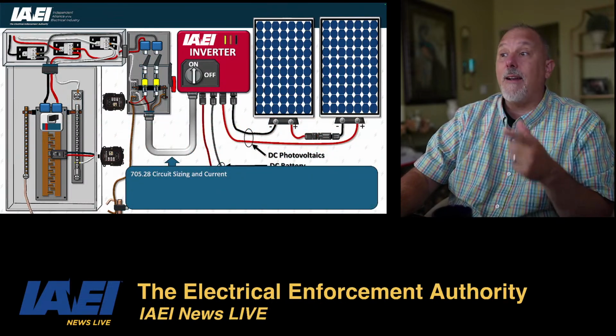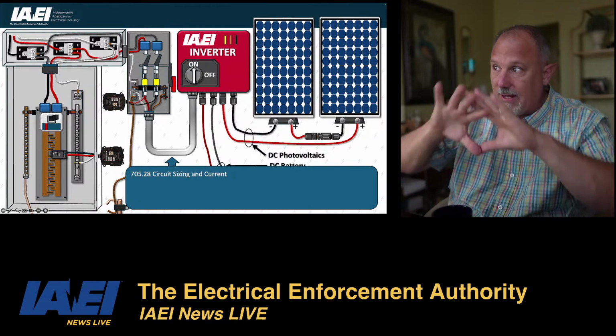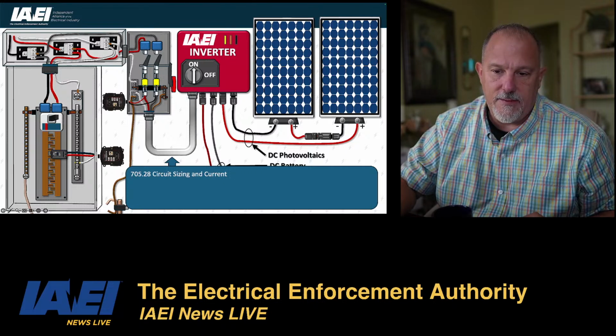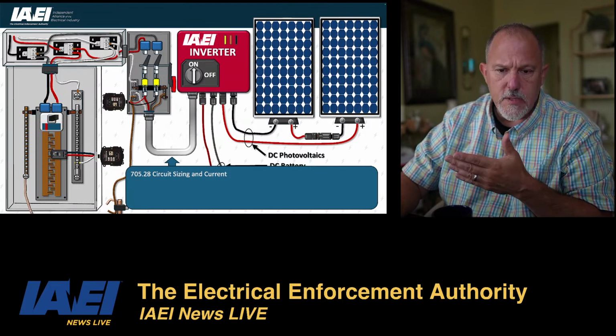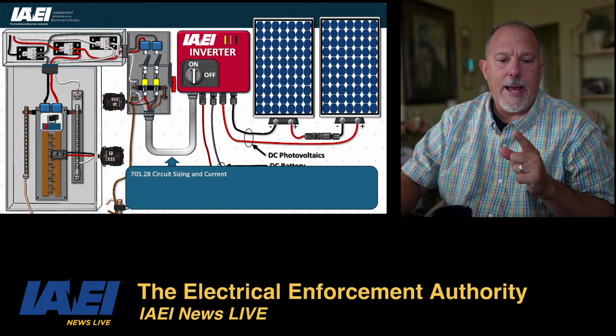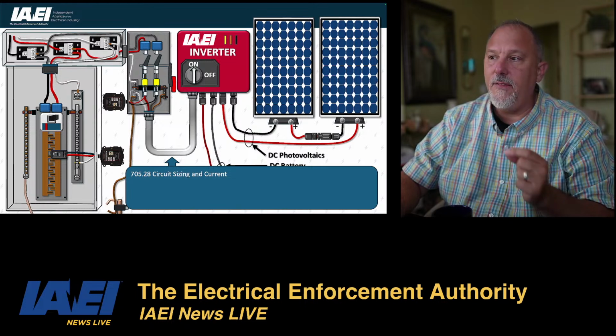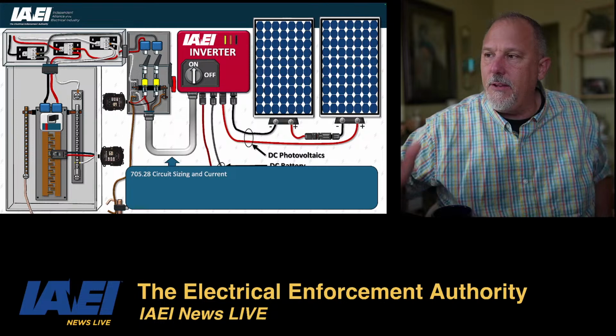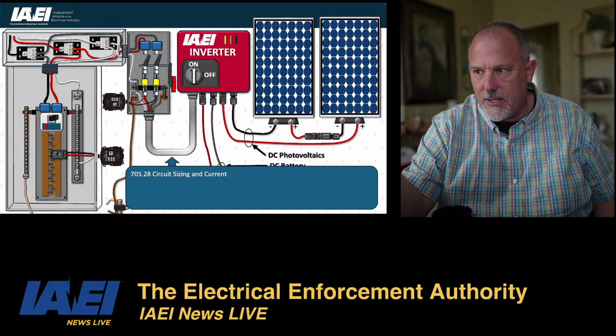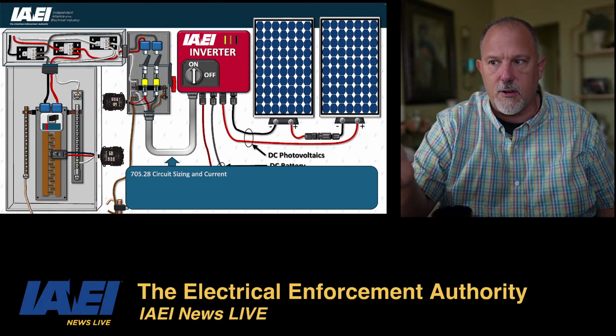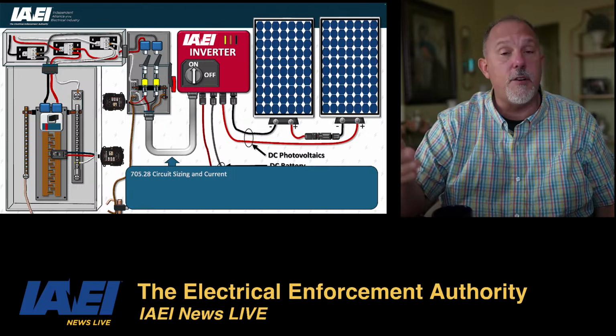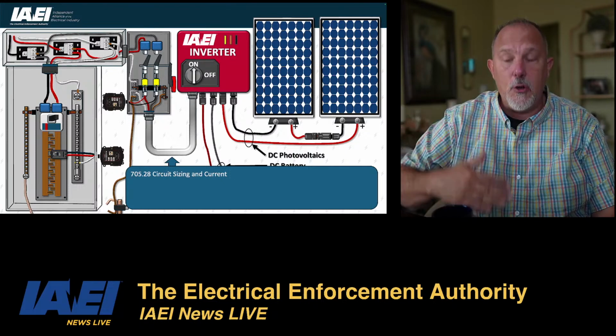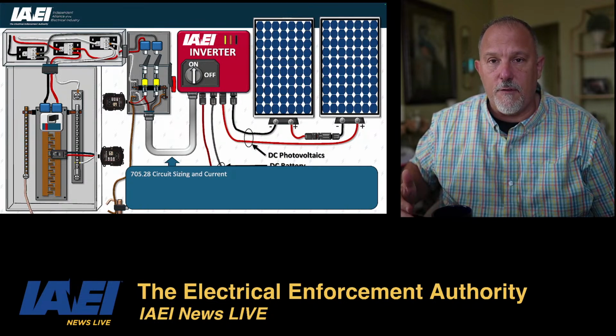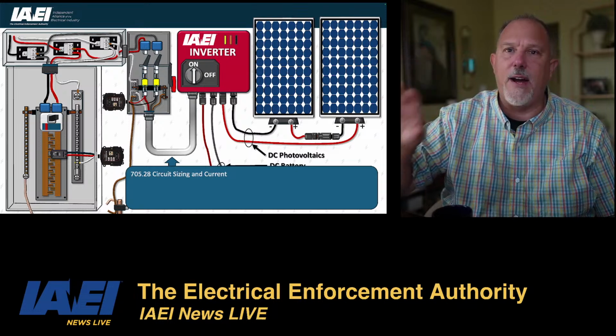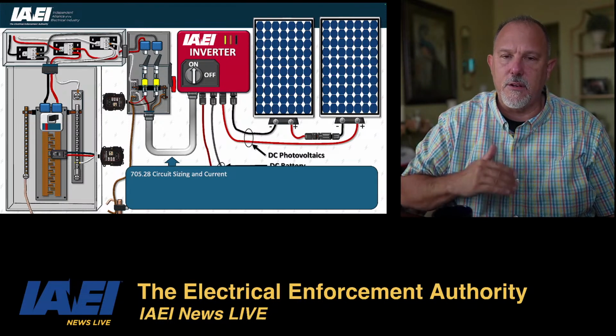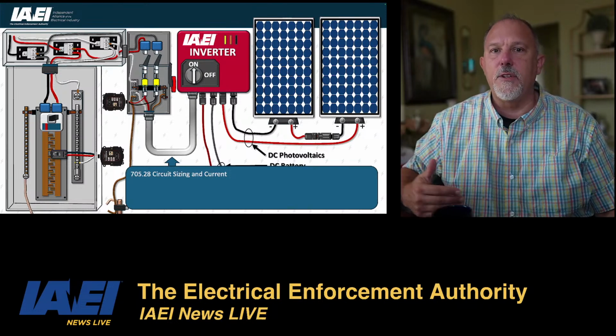Okay, so we've identified the different parts and pieces. Let's talk about 705, and I just started putting this in. 705 has the requirements. Now, 705.28. I don't have a slide for it yet, but I could connect this to, see how that surge protective device in the main panel board is connected to a circuit breaker. I could connect that inverter to a circuit breaker inside of the main panel board. That would be on the load side of the service disconnecting means, which gets you into 705.12. Everything I'm talking about here is 705.11, connecting into the line side of the service disconnecting means. If you're coming into the load side, now you're into 705.12.